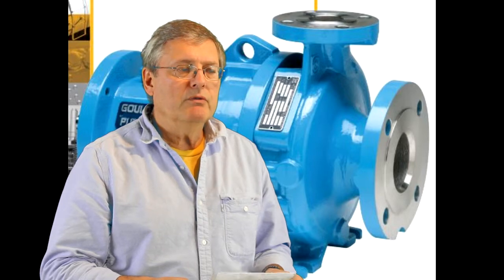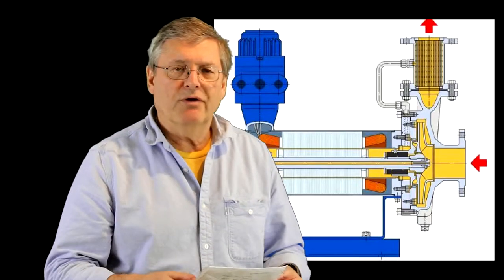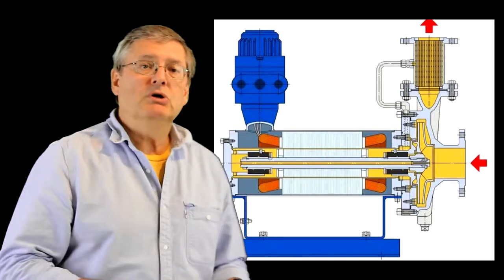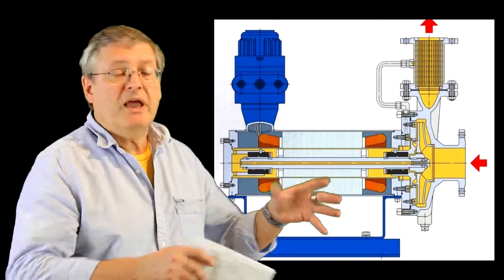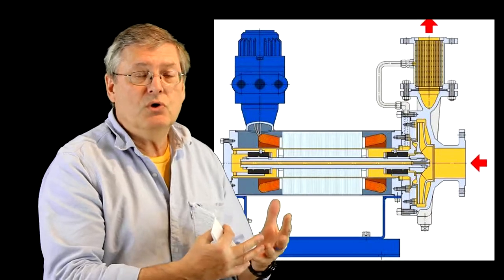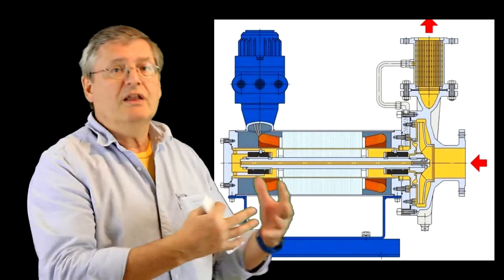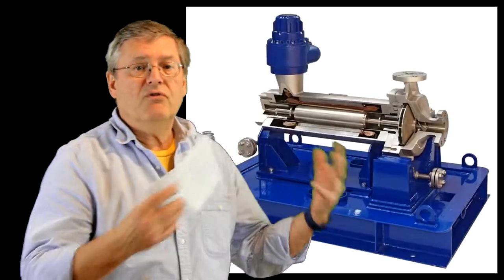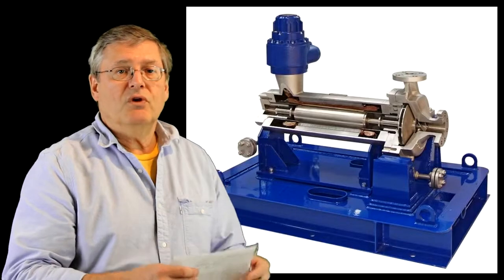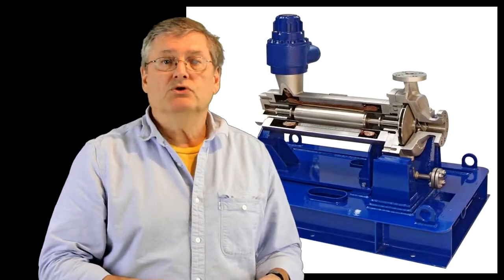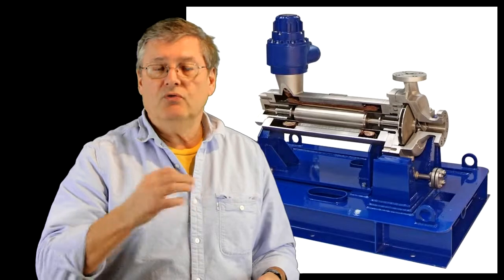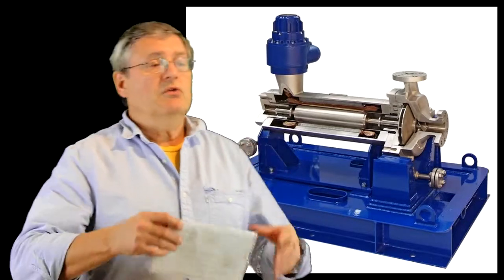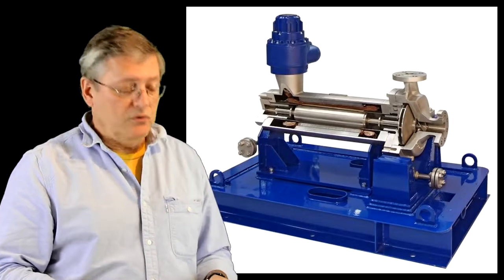If you want to go even safer than a mag drive pump, you would go to a can pump. In this case, everything is enclosed so the motor itself is inside a casing and it drives the pump internally so that you have absolutely no risk whatsoever of having a leakage. From a seal standpoint this would be the ultimate and probably you would use this on extremely dangerous liquids, maybe even very radioactive liquids or things of that nature.